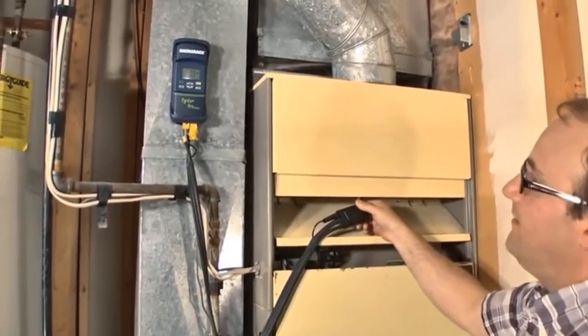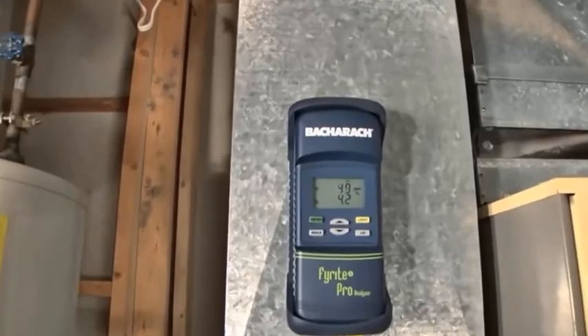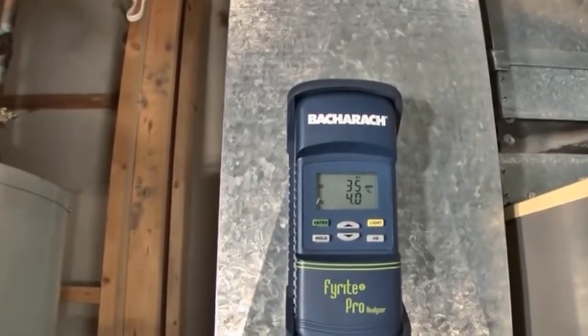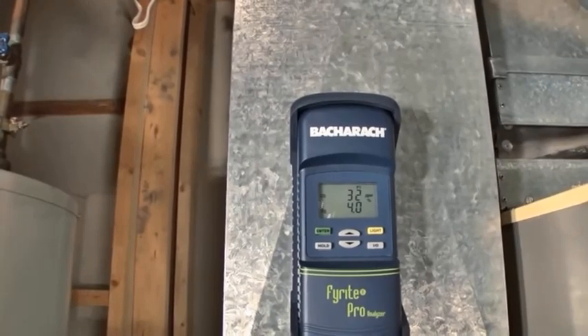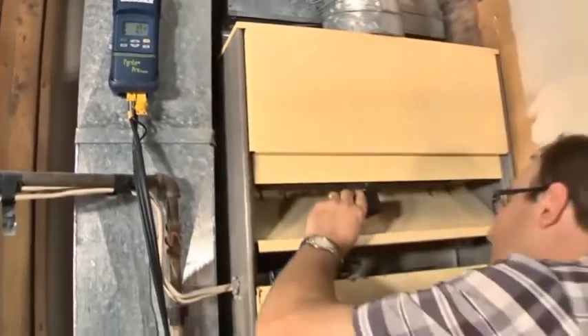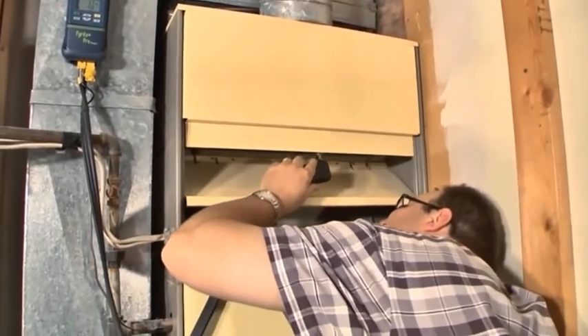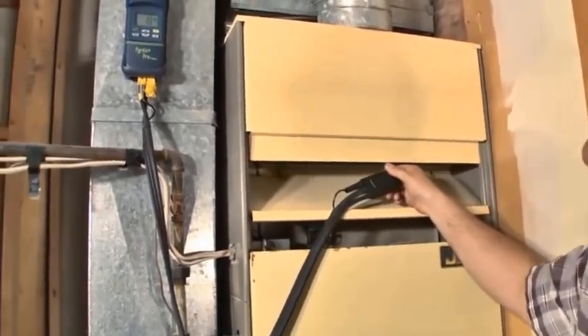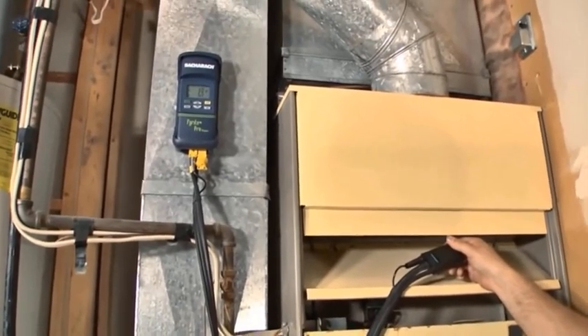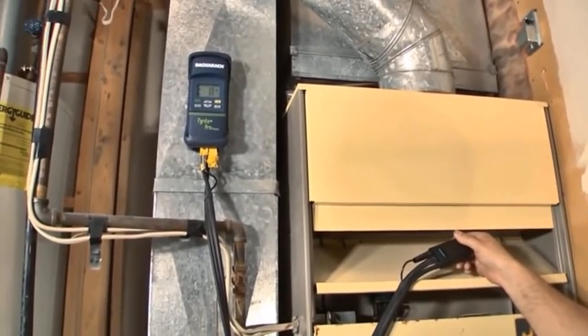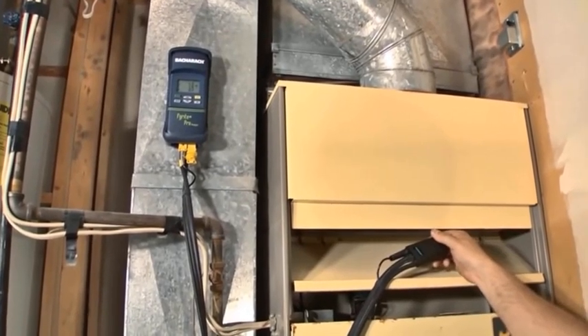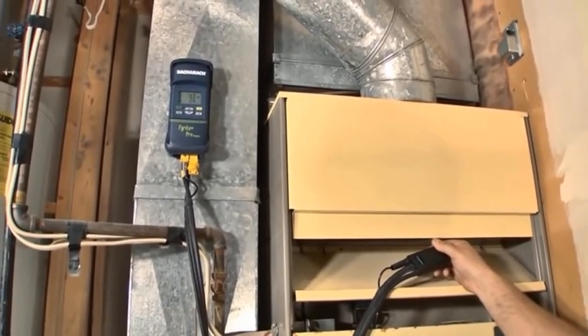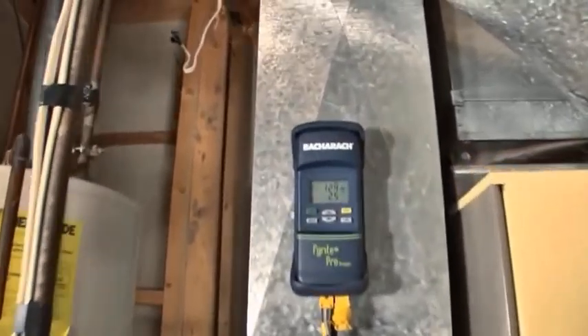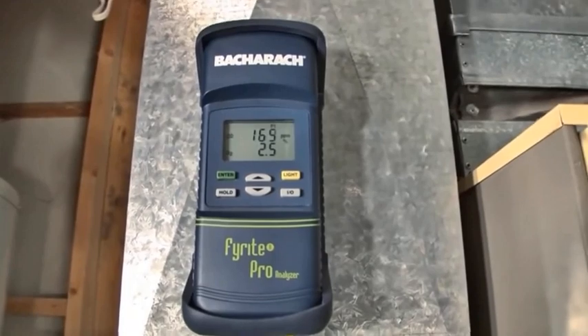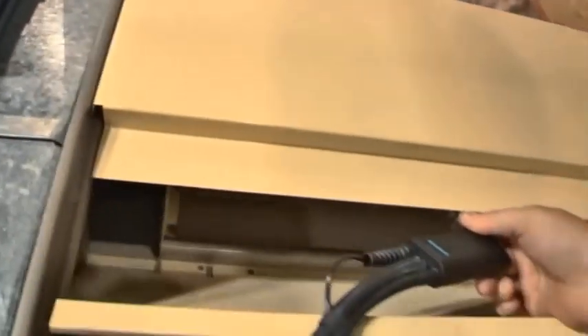Okay, so this is a little higher. I'm still below 100, dropping. It went up and then it dropped back down, but we're in the 30 parts per million range. Okay, I'm going to go to the next one. Okay, so I'm over 100 parts per million here. So this burner right here, I have an issue. This burner definitely has a problem.